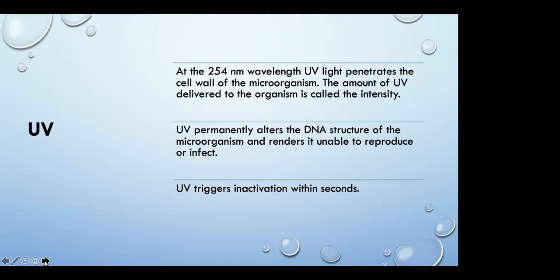UV is another common disinfection method. At 254 nanometer wavelength, UV light penetrates cell walls of microorganisms — the amount of UV delivered is called the intensity. UV permanently alters the DNA structure of microorganisms, rendering them unable to reproduce or infect your culture species. UV triggers inactivation within seconds. The key thing with UV is that it works based on how clear your water is — the transmittance rate. If your water looks like chocolate milk, don't bother with UV because it won't transmit enough photons through that water to do any good.